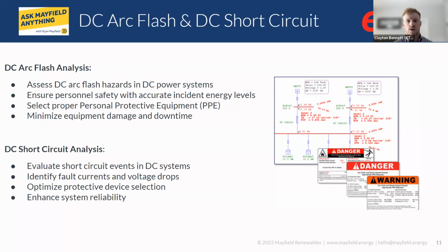Yeah, Victor, I don't know if you want to address the ability to user-define methods for calculation. Yeah, the calculation methods included in the software are three, the three that Clayton mentioned. There is no IEEE or NEC standard available for direct current arc flash, but we do use one that is extremely conservative. It's called the Stokes and Oppenlander method. It's included in the program. This is user selectable, and it does take into account things like the distance between your electrodes, and it's extremely accurate. We have made improvements to this for PV systems. So you can rest assured that, for example, the incident energy or the labels produced with this particular module are very close to reality.